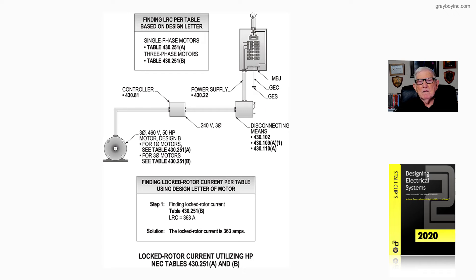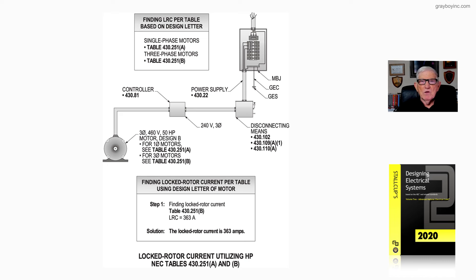We could round that up to 400 amps if you wanted to, divide it by 3 for a circuit breaker, and then round up to the next size circuit breaker. You could take the 400 amps, divide it by 5, and round up to the next size fuse. These are good rules of thumb to use without even having to go to your codebook.